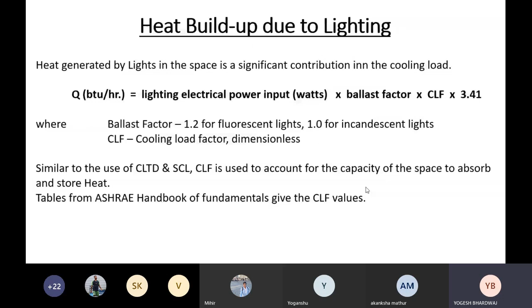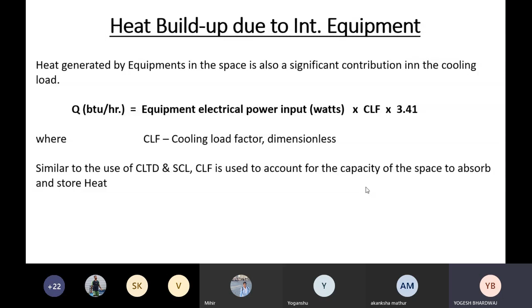Then with this equation, you can calculate the heat buildup due to the interior equipment that is there inside my thermal space. So I should know the power input of those electrical equipment, and then I can use the CLF values and then the 3.41, a constant unit conversion factor, and I can evaluate the heat buildup due to equipment in BTU per hour. Then heat buildup due to occupancy.